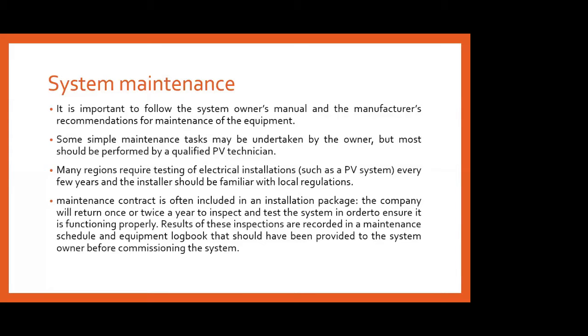Many regions require testing of electrical installations, normally the PV system, every few years, and the installer should be familiar with the local regulations. When the commissioning has been done by the installer and he is handing over to the customer, there will be a maintenance contract between the installer and the customer, that is, the company which installed the complete PV system. A mutual understanding or maintenance contract will be made for a few years.